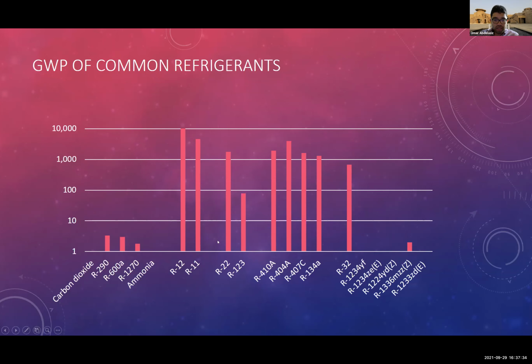And then for HCFCs, like R22 and R123, you can see R22 is close to 2,000 and R123 is close to 100. For HFCs, they are all higher than 1,000, and the highest of them is R404A, close to 4,000. Then we have what we call the low GWP refrigerants, starting with R32 at about 700, and all of the others are close to 1, except for R1233zd, which is about 3.